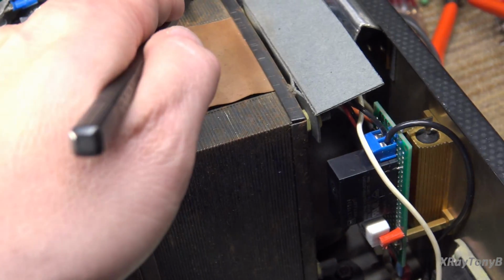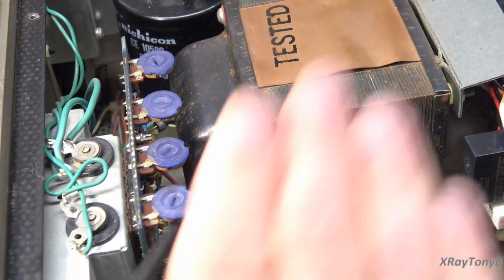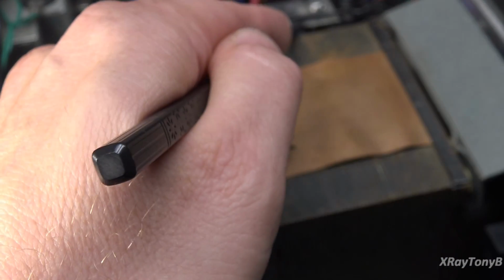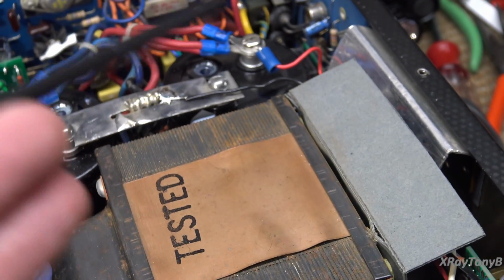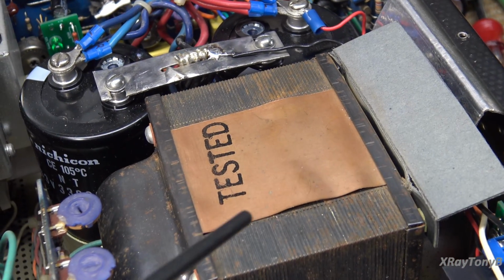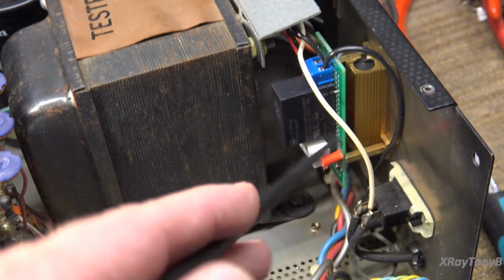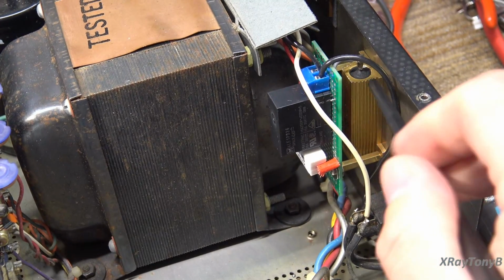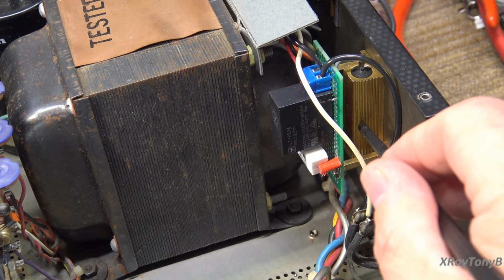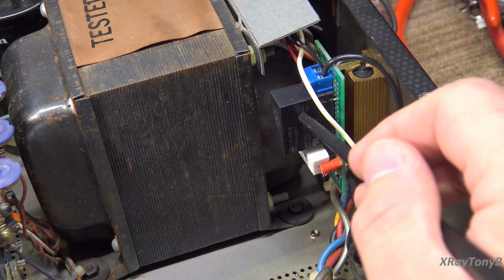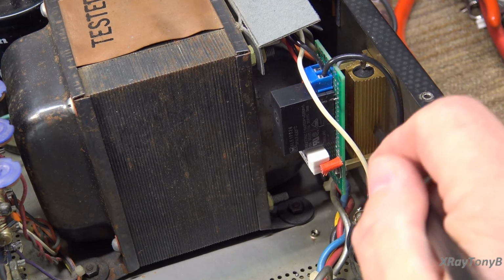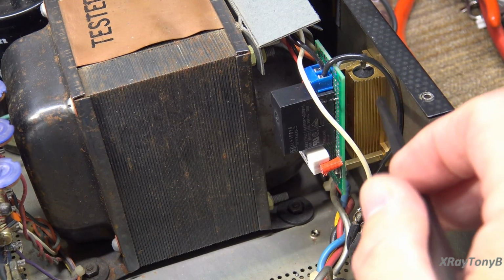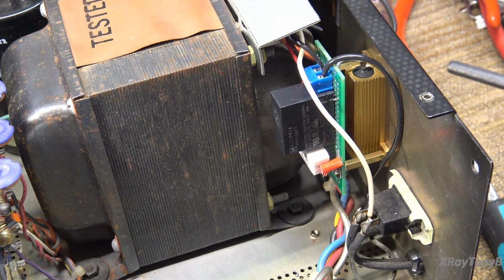If that's the case, a capacitor doesn't charge linearly. In other words, the highest current draw it's going to have is when it has the lowest voltage across it. Once the voltage begins to build up, the current begins to drop down. Once the current drops down, the voltage drop across this resistor goes way down. So when these contacts close, you're just clamping out a small voltage drop across here relative to what it would have been when it first turned on.